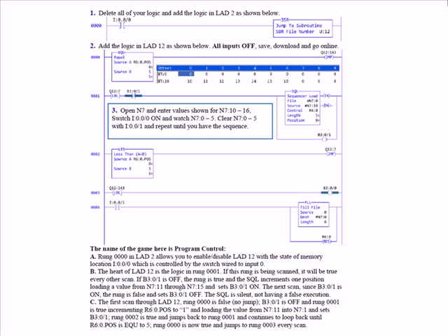Rung 2 is still true, which causes us to jump backwards one rung to rung 1. Now, since we just turned B31 off, that instruction will be true. We'll execute the SQL and set B31 back to 1, which means that every other time that we execute rung 1, it will be true, and every other time it will be false.